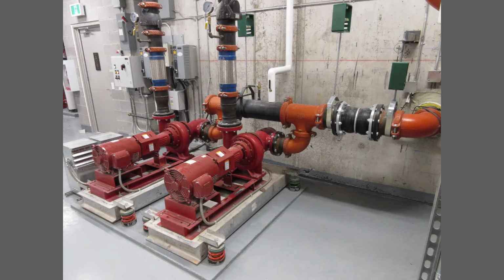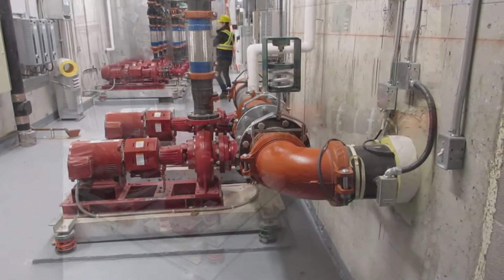As required by the project documents, the pumps are supported by concrete inertia bases on open floor springs and have flexible connectors on both the suction and discharge piping. We'll go ahead and walk around the installation, focusing on the flexible connectors, and then look at the data sheets and installation instructions. After that, we'll take a closer look at the double sphere expansion joint flexible connector on the suction pipe and discuss what we should be looking for during a site visit.